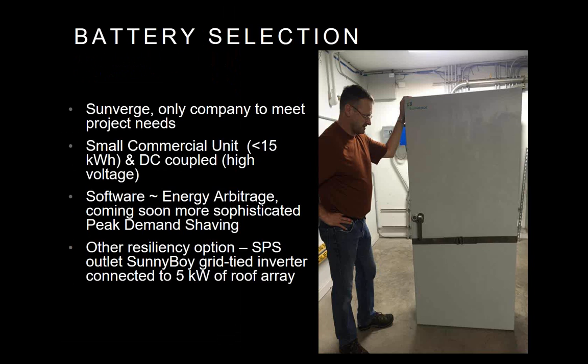We still had the other half of the array where the inverters needed to be repaired and hooked back to the grid. What we decided to do was install a Sunny Boy inverter with a secure power supply, an outlet that the rooftop array can power if the grid is down, with a certain amount of energy. That adds to the resiliency features of the emergency shelter, and we're pleased with how it works. It was just installed about two weeks ago, and we'll be able to test out that secure power supply to see how it can best be used in resilient, emergency situations.